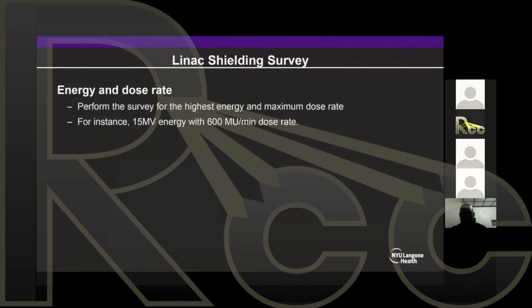And regarding energy and dose rates, you're always gonna do it like worst case scenario. So you're gonna perform the survey for the highest energy and the maximum dose rate. So for instance, we use 15 MV with 600 MU per minute.